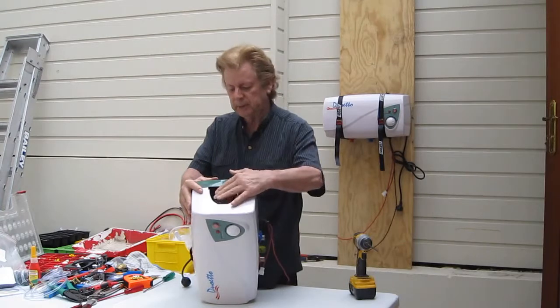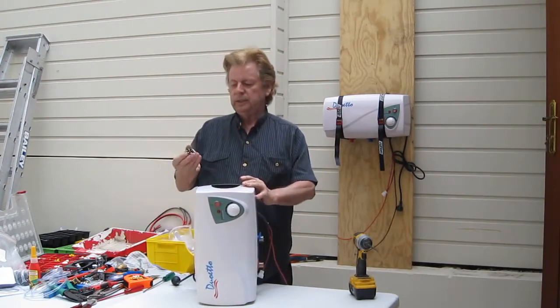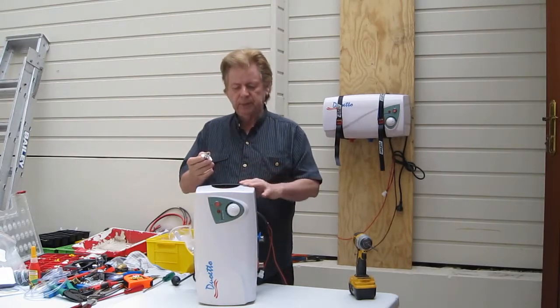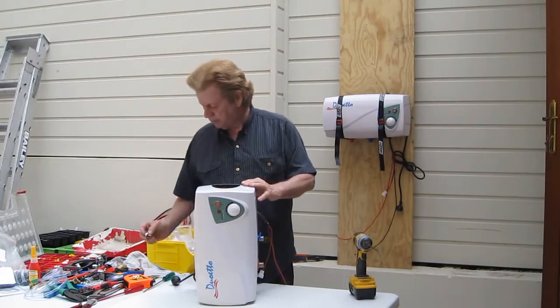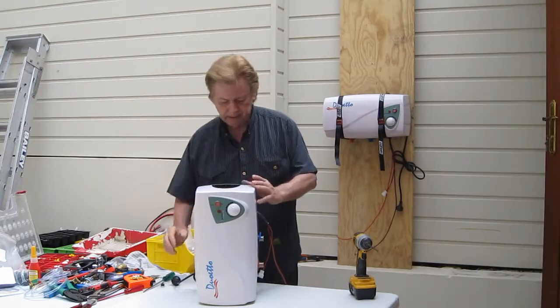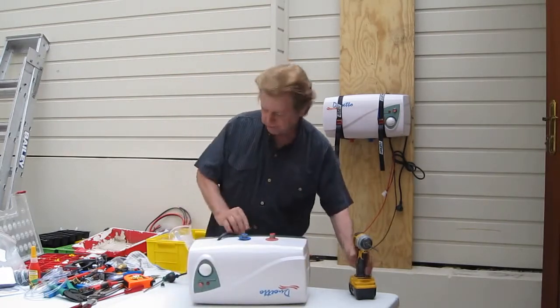To fix the problem is the reset button, which is accessible by this inspection plate, and it looks like this. I'll split the casing so you can actually see the location of this and the 12 volt one as well. The 12 volt one is a little bit smaller — it looks like this. I'll clamp it up and show it to you.